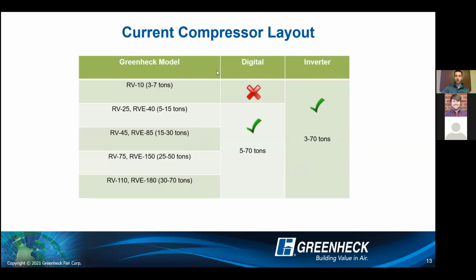And then here is the current compressor layout. Basically, there is one area where we already made this change. I talked about the new model being the RV10. Because of the Department of Energy efficiency values coming down the pipeline in that 2023 timeframe, we didn't even want to design this unit with a digital scroll compressor. So that one will be standard an inverter compressor always, all the time. The other housings, we still have that option to select your lead compressor as digital scroll, again giving you that good capacity control. But we do still have 5 to 70 tons as an option for that inverter compressor as well. So you can still get that option.